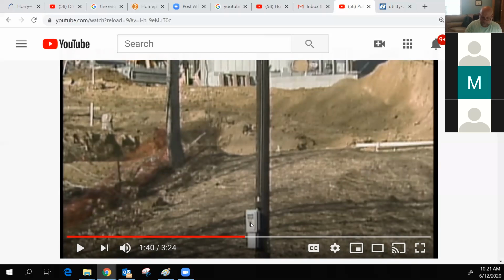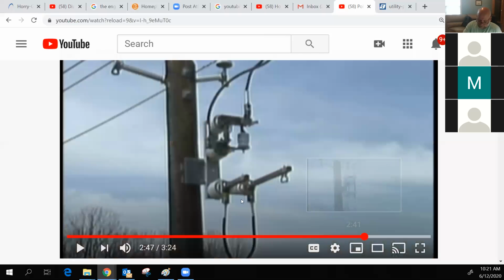And you want to make sure that one or all of those methods are used, because you don't want to be in the bucket above it while it's in the raised one, and then you open or close that bypass, because it's going to be a bad day for somebody. So make sure the regulator is in a neutral position before you open up these as well, because what you're doing is breaking load on that feeder.